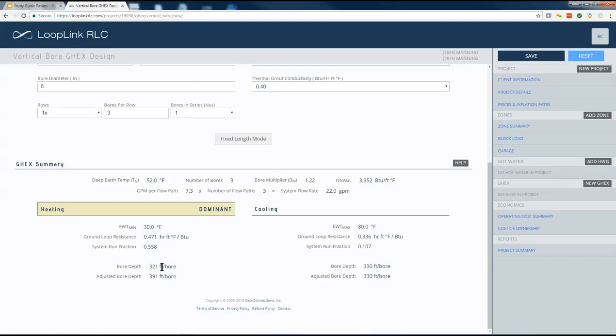The bore depth is the amount of pipe, theoretically, that you'd have to put in the ground to satisfy your heating constraints and satisfy your heating loads given the layout that you've provided here the first year of operation. The adjusted bore depth accounts for that ground load imbalance, so this is theoretically how much you'd have to put in the ground to satisfy all your constraints and account for the imbalanced ground loads over the long term, over the life of the system.